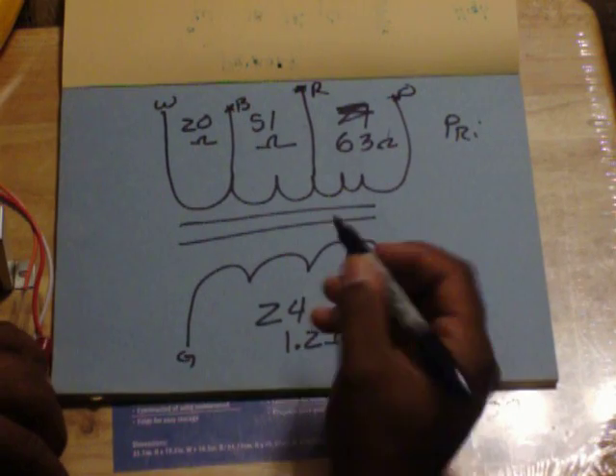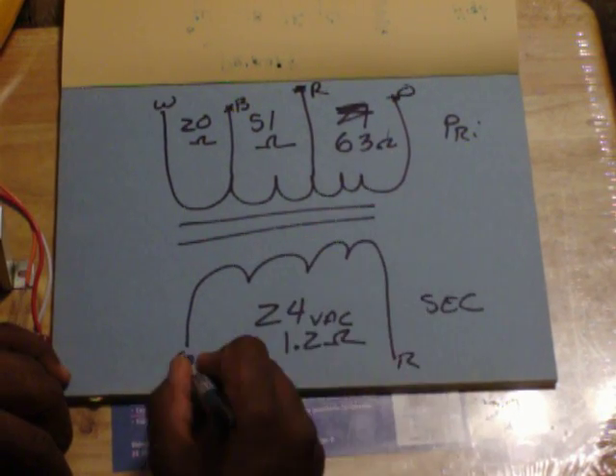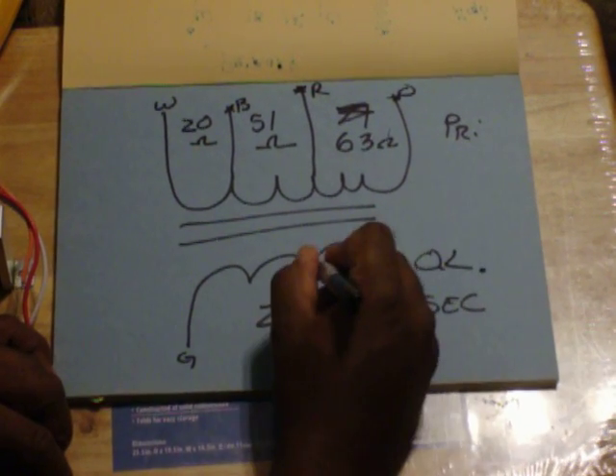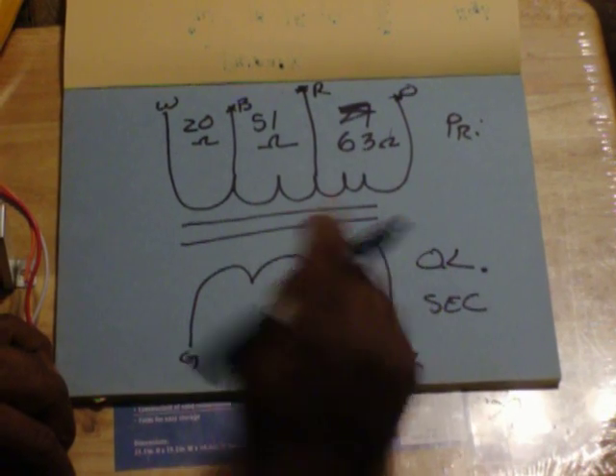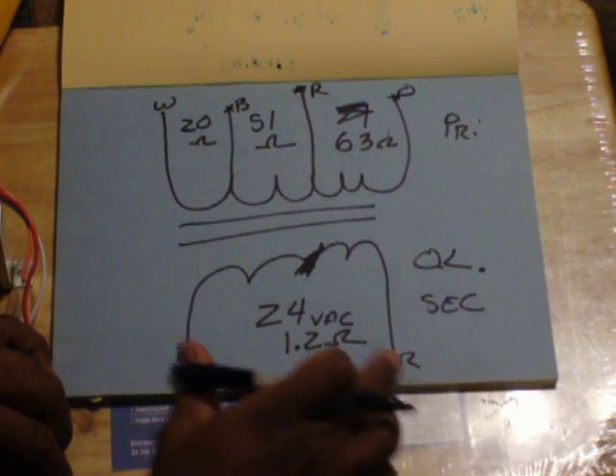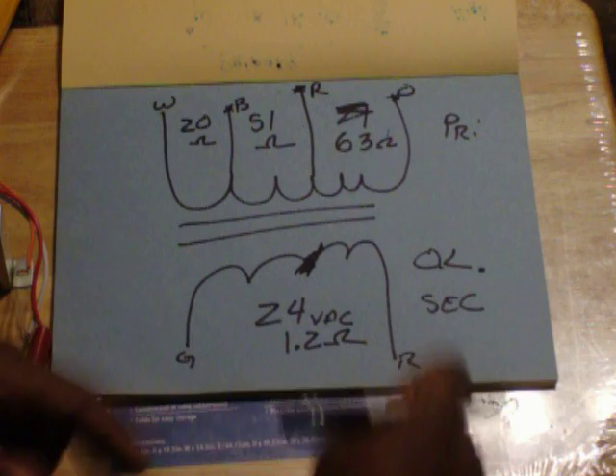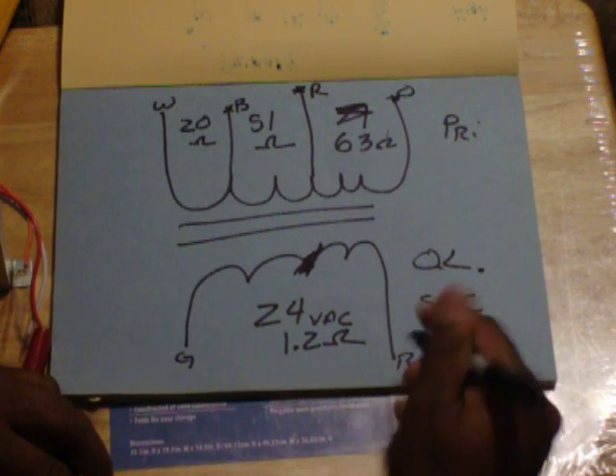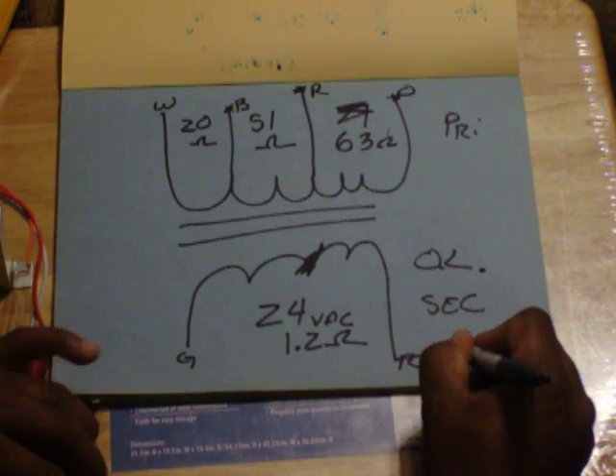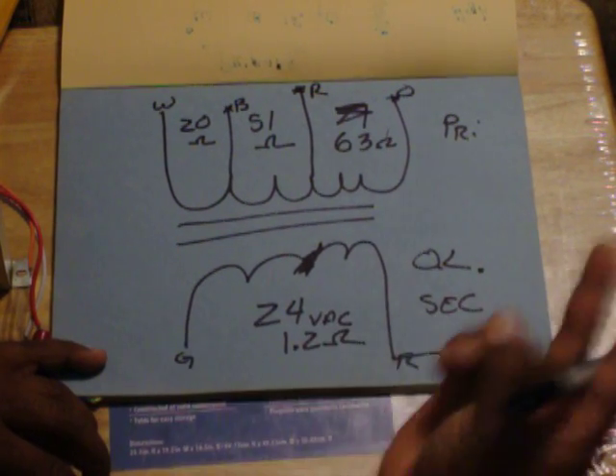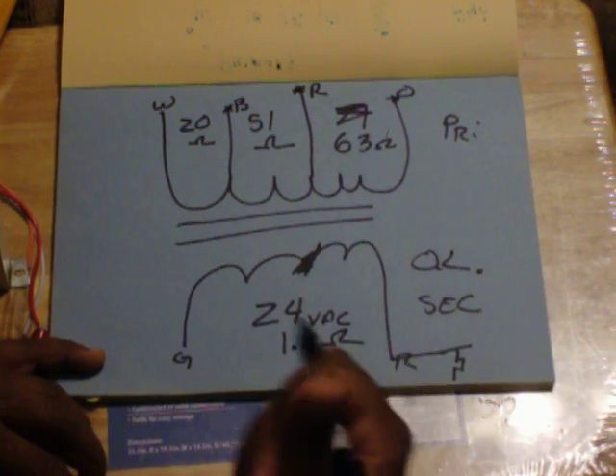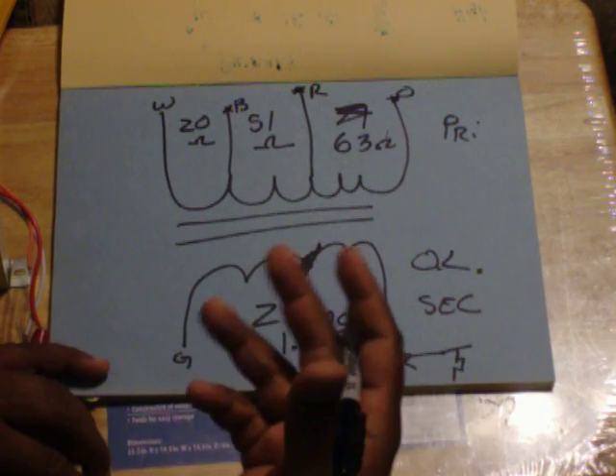My caution here again. If you check from green to red or whatever your color is on yours and this reads an open line, OL, that means your secondary was burnt out. If your secondary is burnt out, something down here and all it feeds there, this goes to your thermostat and then your thermostat feeds your blower relay and your contactor. Your blower relay is shorted out, your contactor is shorted out, one or the other.